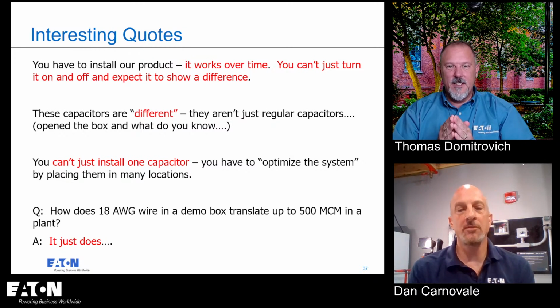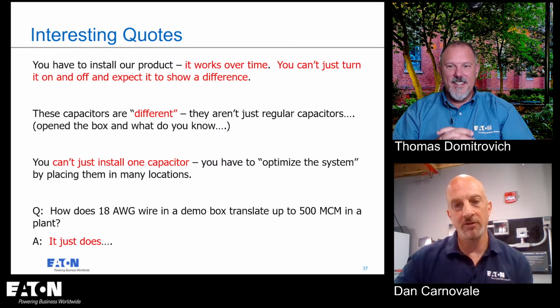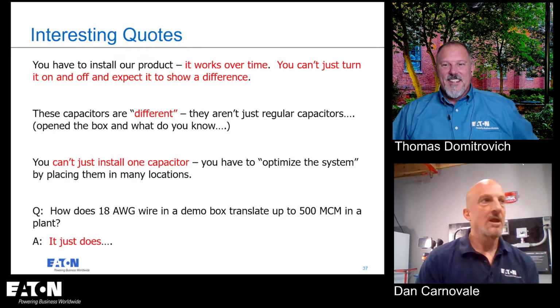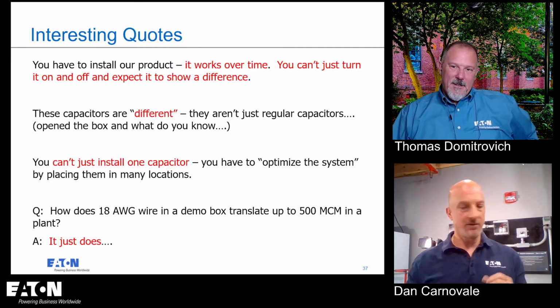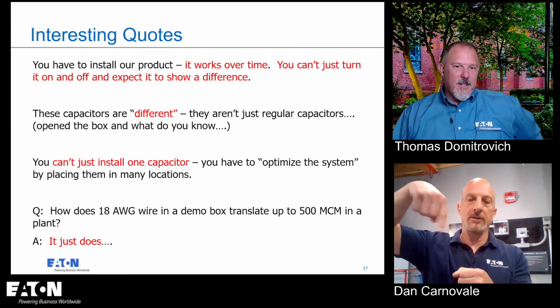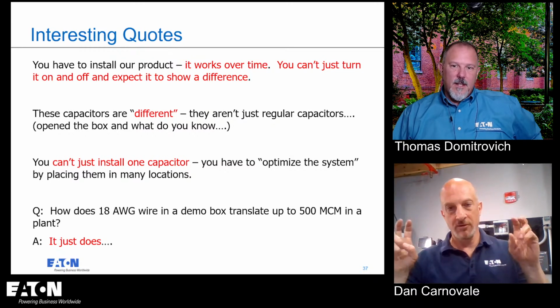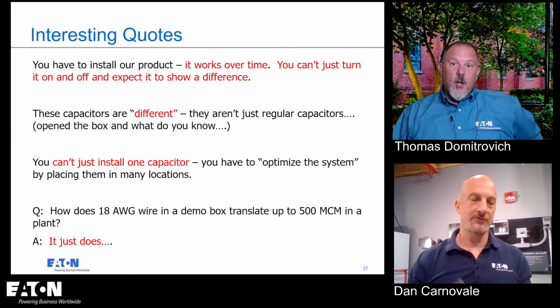So I opened up the box. I drilled out the rivets, because they always rivet them shut because they really don't want you to look at them. I opened them up. It looked like somebody took a broom handle and coiled a piece of wire around it, like a 10-gauge wire, and that was their harmonic filter. It was an air core filter.